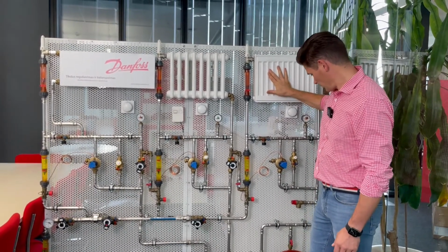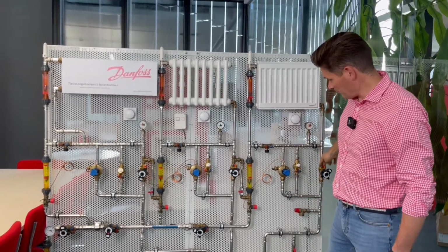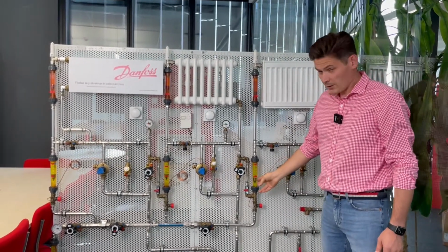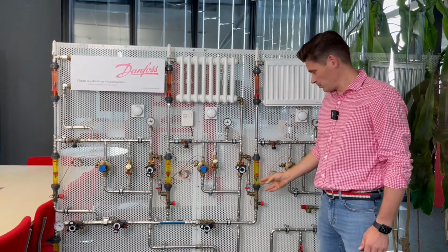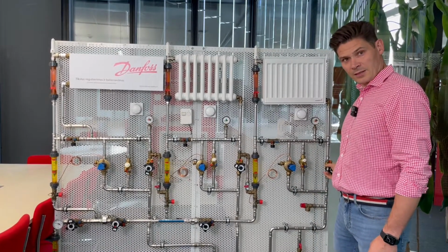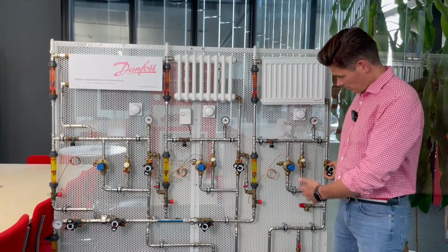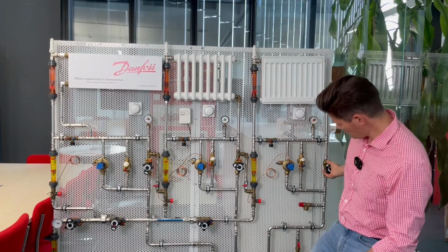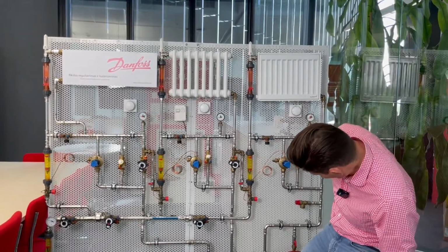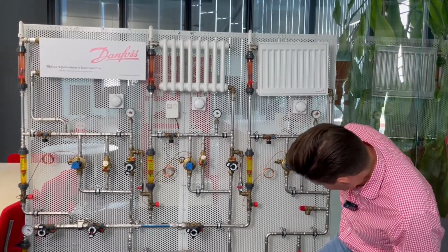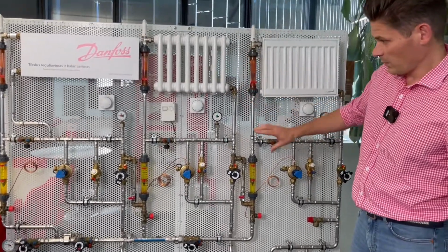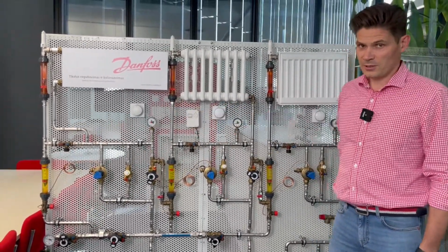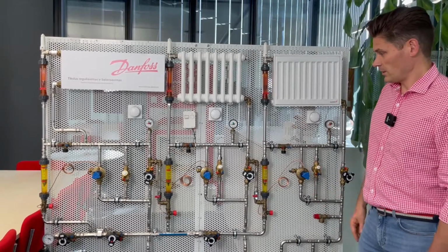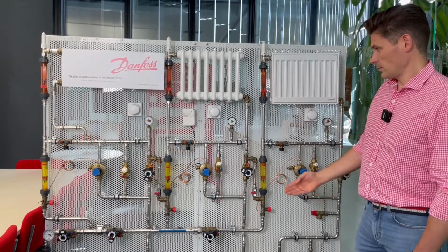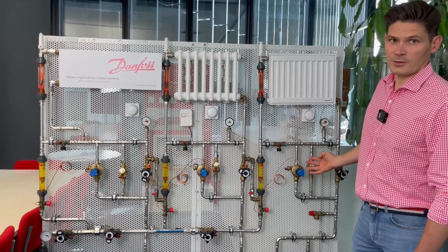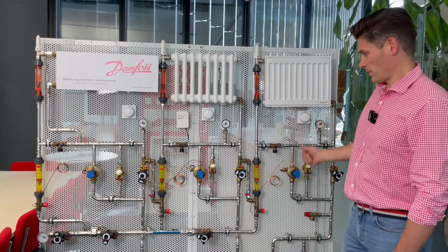The maintenance company comes, they connect to the manual balancing valve, and they see there is really not enough flow. What to do? We need to open up the balancing valve. Now they open the balancing valve and set 200 liters. Now everything is open and everywhere we have 200 liters. So at full load, when everyone is open, we have our design flow of 200 liters for each riser.